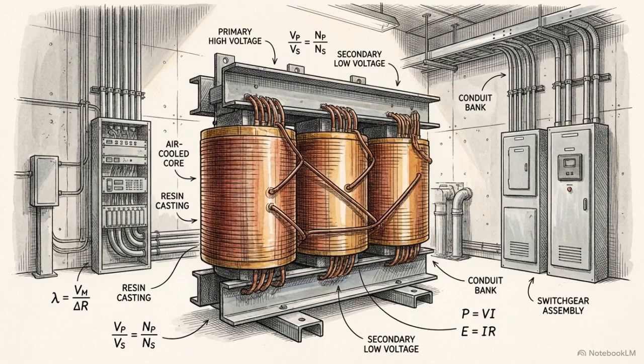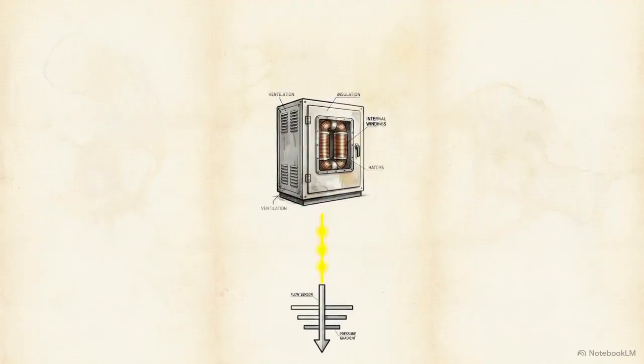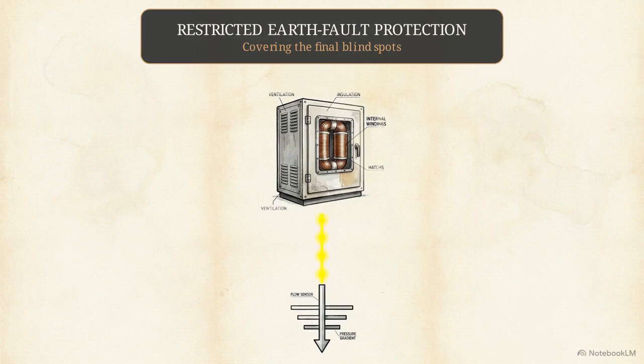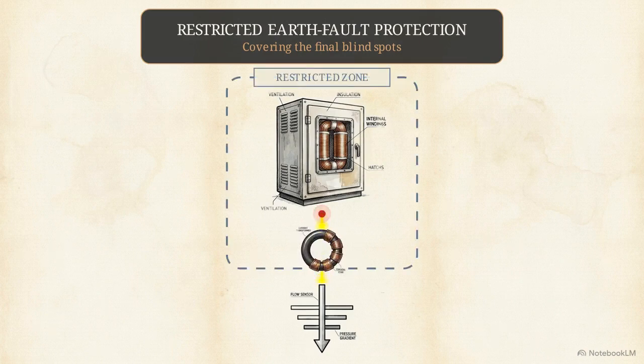In its current operational state, this network of relays and sensors will detect abnormal conditions and isolate faulty equipment faster than you can blink. Understanding dry-type principles and applying these exact configurations turns a fragile machine into a resilient powerhouse. Next, we will coordinate this setup with restricted earth fault protection to cover the final blind spots.